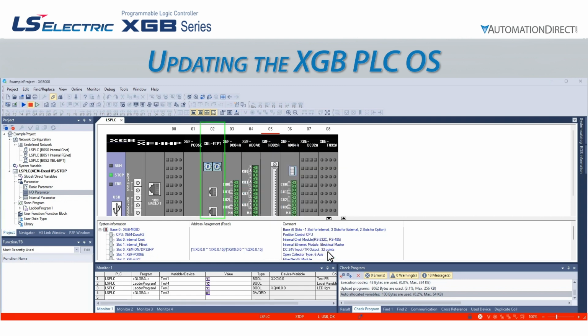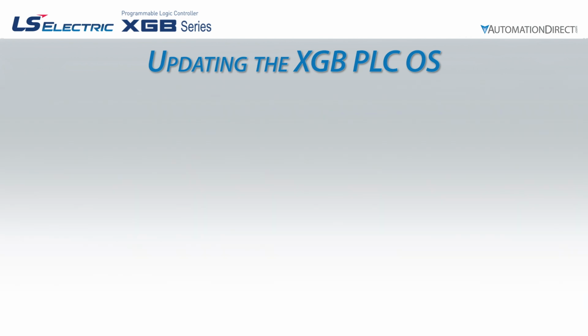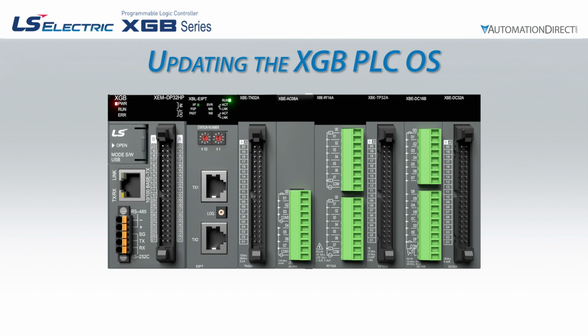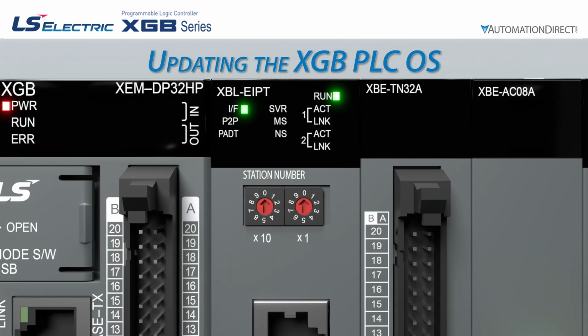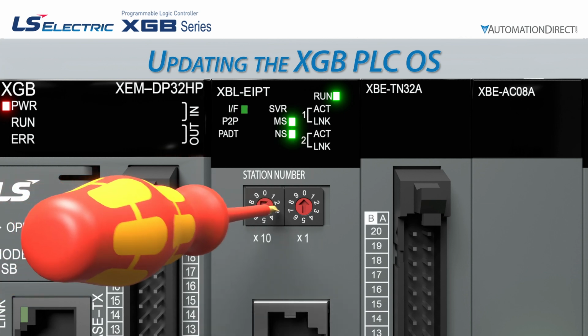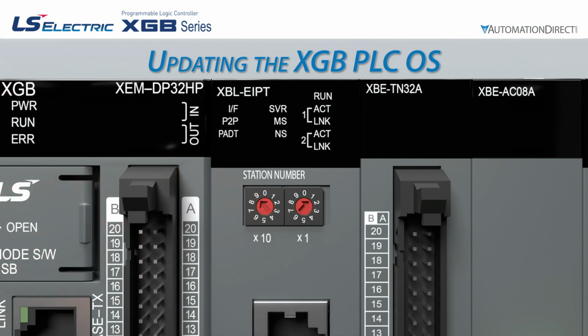Some modules, such as the XBL EIPT Ethernet IP Communication Expansion module, use the XG5000 software to update their OS instead. To perform this update in the software, we first must put the hardware into boot mode. To do this, we need to record the current station number dial positions for X10 and X1, then put them to 91. We then need to power cycle the PLC rack and wait for the LED lights on the XBL-EIPT card to blink in a rotating pattern indicating boot mode.